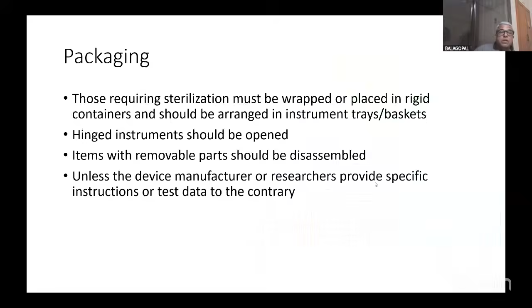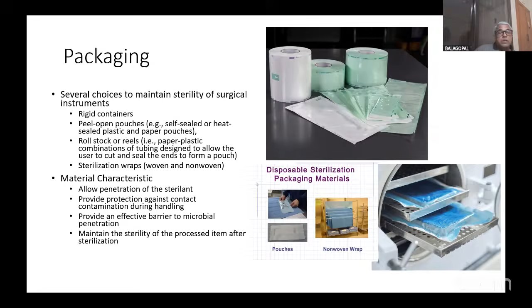For packaging, instruments requiring sterilization must be wrapped or placed in rigid containers. Hinged instruments should be open. Items with removable parts should be disassembled, unless the device manufacturer or researcher has provided specific instructions. There are several choices of packaging material: peel open pouches, rolled stock or reels, sterilization wraps. They also have particular material characteristics which allow penetration of the sterilant and provide protection against contact contamination during handling. So these are some of the ideal sterilization materials.